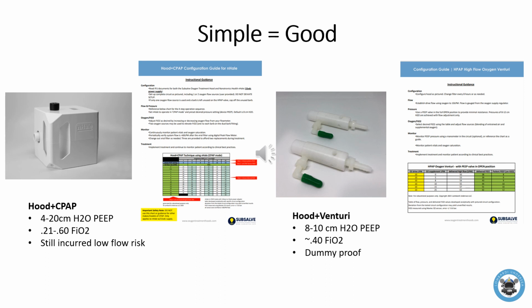A couple of the Italian companies offered medical Venturi valves with their hoods, but those valves were not available in the United States. So I went ahead and engineered our own valve. It's a pretty nifty contraption. It uses the Bernoulli principle. Basically, you connect oxygen up as the drive gas at low flow, and based on the shape of the valve on the interior, it works to entrain room air and create a high flow. So we'd input about 8 liters per minute of oxygen and cumulatively get out to the hood around 50 liters per minute. So it's a pneumatic solution to driving the hoods with a sufficient flow source. I was very excited about that development.